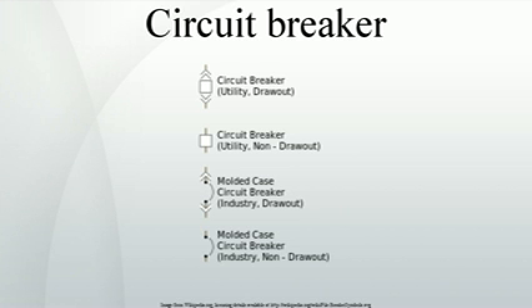Sulfur hexafluoride, SF6, high-voltage circuit breakers. A sulfur hexafluoride circuit breaker uses contacts surrounded by sulfur hexafluoride gas to quench the arc. They are most often used for transmission level voltages and may be incorporated into compact gas-insulated switchgear. In cold climates, supplemental heating or derating of the circuit breakers may be required due to liquefaction of the SF6 gas.